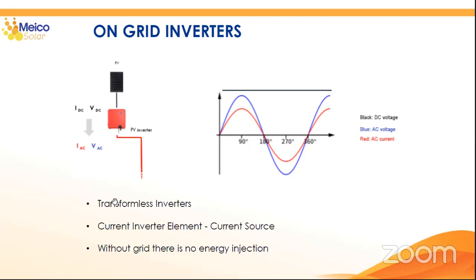This is very important: if you don't have a grid, you can't inject energy. Why? Because you don't have the reference of the grid to inject the current the way the grid needs it. So when you don't have a grid, the on-grid inverter will be completely lost and can't deliver that energy. It's not only for safety reasons, it's also because you lose the reference and then you can't inject the energy properly. This is very important with on-grid inverters: no grid, no energy injection.